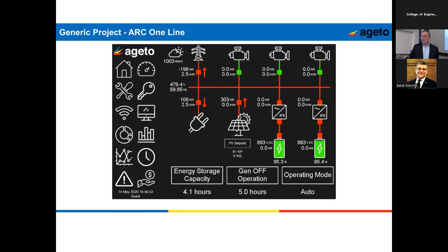The reason I show this chart is all this becomes seamless. It's automatically controlled by the microgrid controller, and it's set up so you can set up whatever you want it to do. We can set it up as backup power. We can set it up to buy power from the grid at certain times of day, export power at certain times of day to optimize the return on investment. So it's very flexible. And on this, we worked with a company called Ageto. They're in Colorado.